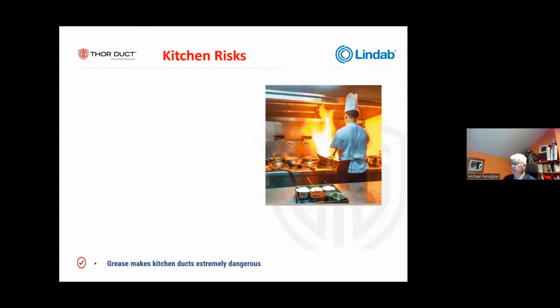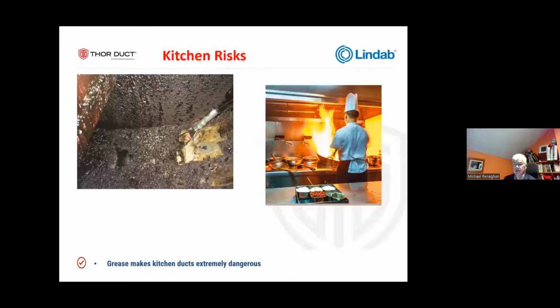The other area we're concerned about is a thing called the kitchen extract. So in the kitchen, there is a known risk, and that risk is the grease. So grease will, over a period of time, congeal on the inside of a duct. Now, the issue with grease is that the oils that we use for cooking, most of those have a flash temperature in excess of 350, 400 degrees. However, when you heat up oil and cool it down, heat it up and cool it down over a period of time, you do a thing called oxidization. And in the process of oxidization, you lower the flash temperature down to 180 degrees. So that's a significantly lower temperature at which it will ignite.